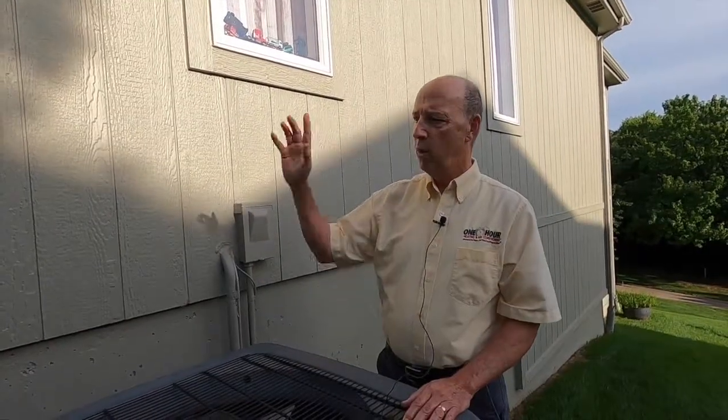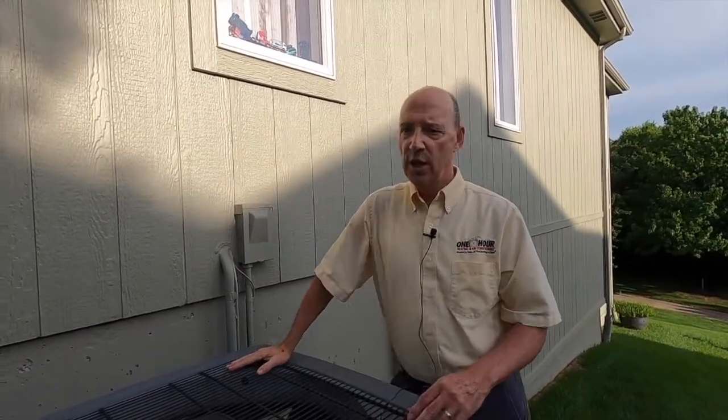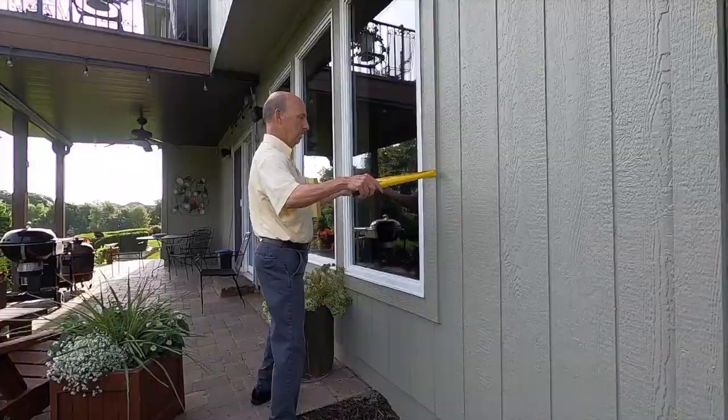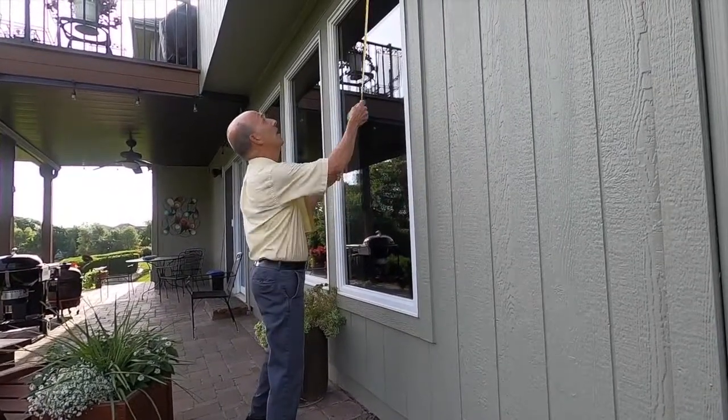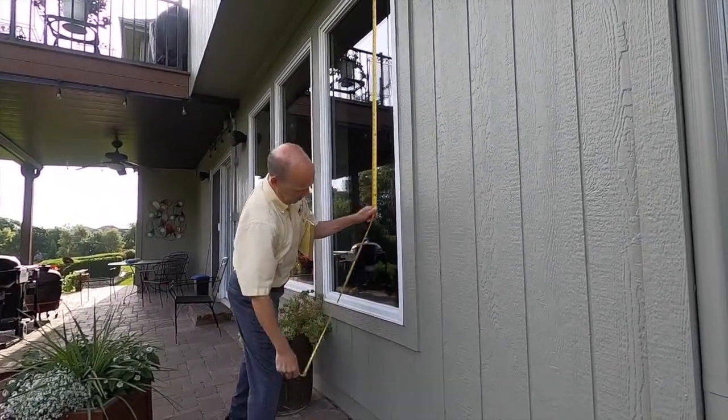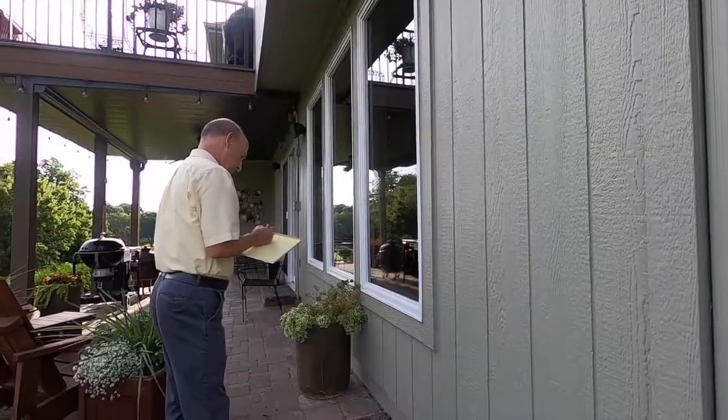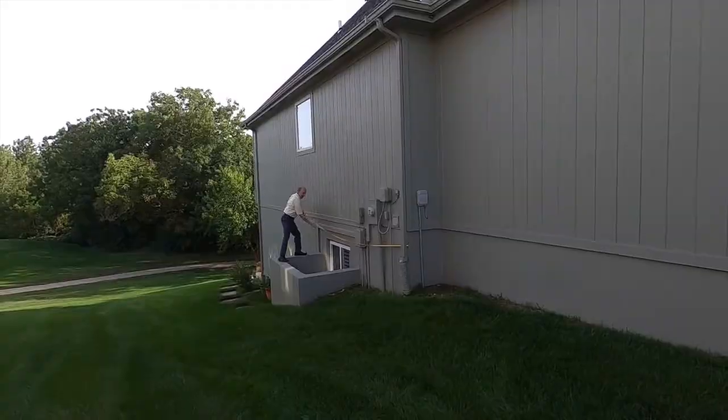You could have two identical homes, and one's on the north side of the street, the other, same home, right across the street, but their window exposures are now exactly the opposite of the first one. Now all those windows are facing the south rather than facing the north. Well, that's a huge difference in the calculation for the air conditioner, and it can even be a big difference on the furnace side of it. I've got all these windows facing the north wind versus being exposed to the southern sunshine in the wintertime.